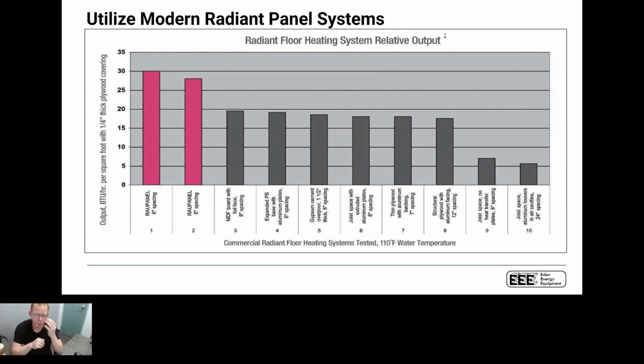So if you remember back to what we said about how houses have lower and lower loads, we don't need 30 BTUs per square foot as long as they close the windows in the wintertime. So the reality is we have the ability to pull that water temperature back. And in my own home with the Rehau panel system, I actually had sub 90 degree water that was heating the space because I didn't need 30 BTUs per square foot going into that space. So air to waters are new technology, but dry panel systems like this that you can utilize have been around a long time, and they really, really matter with an air to water heat pump.